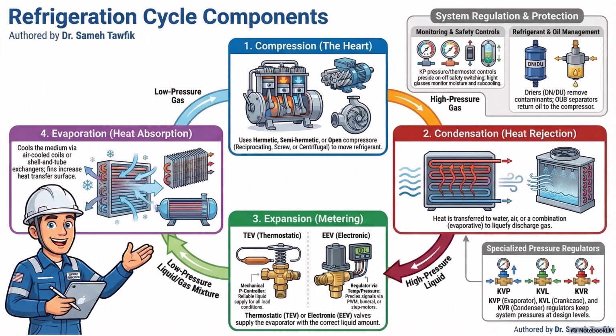So the metal has to touch the air. Yes. The metal of the evaporator must physically touch the medium. That's why evaporators are completely covered in thin metal fins. To massively increase the heat transfer surface area. Exactly. The diagrams in Dr. Tawfik's notes show ceiling-mounted versions that rely on natural circulation, where cold, dense air just falls naturally, and then there are forced air versions with massive fans blowing across the fins.